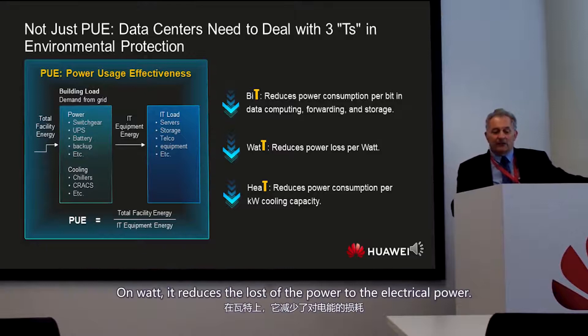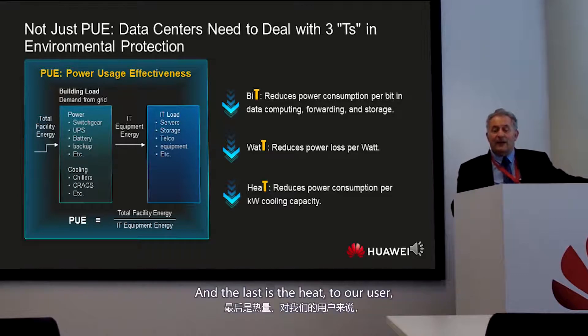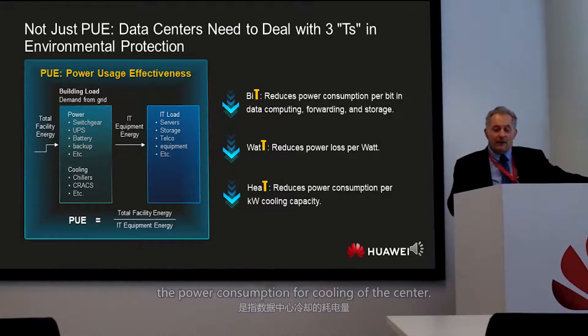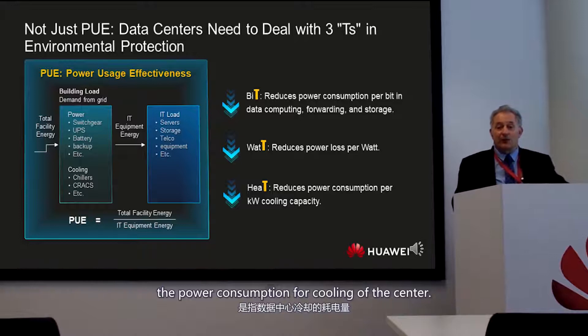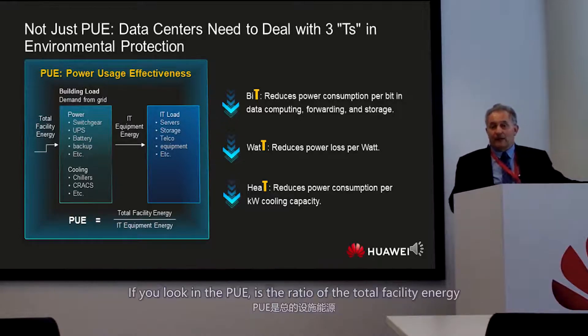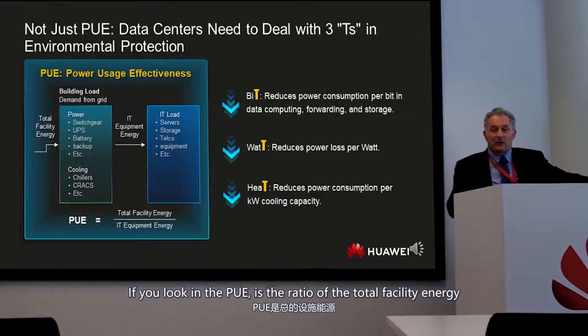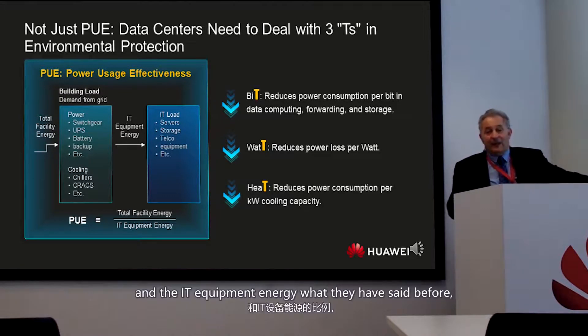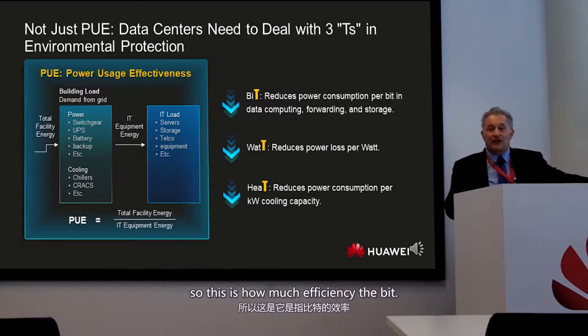The watt dimension is about reducing the loss of power during management of electric power. The heat dimension is about reducing power consumption for cooling. PUE is the ratio of total facility energy to IT equipment energy, so it doesn't capture how efficiently bits are processed.